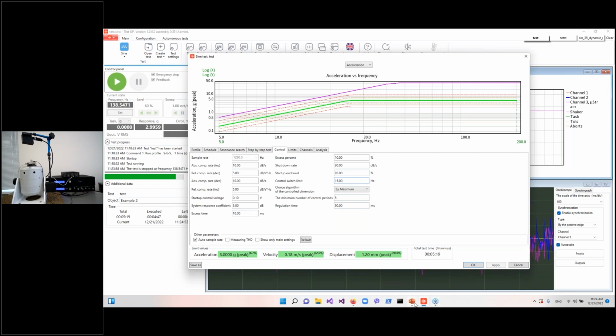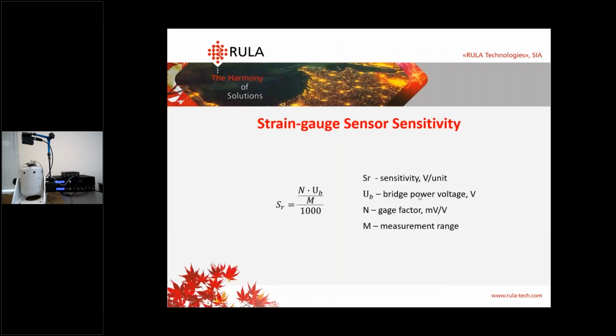So let's go back to our presentation. And about strain gauge sensor sensitivity. It is calculated automatically in our software, but you need to have some data for this calculation. First of all, you need to know the sensitivity unit. In our case, it's microstrains. We need to know bridge power voltage. We need to know gauge factor and the measurement range. All these data are shown in the sensor passport.